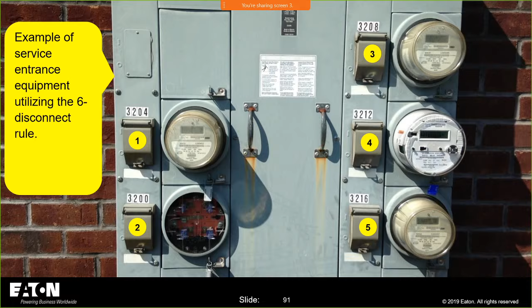So now you take a look at that piece of equipment. If you take that center, that's a meter center. If I take that centerpiece off, I'm looking at exposed bus. I don't have the ability to put an arc reduction maintenance switch in there. I don't have the ability to say it's barriered. That's exposed, energized conductors that aren't protected by an overcurrent device other than what's on the line side of the utility transformer. So what happened to institute a lot of these changes?